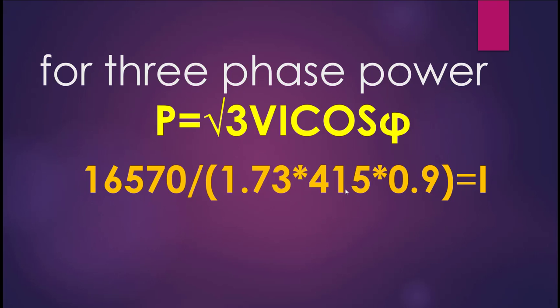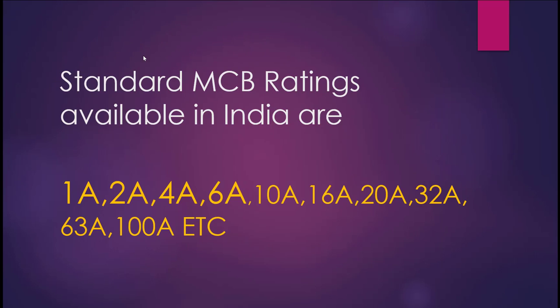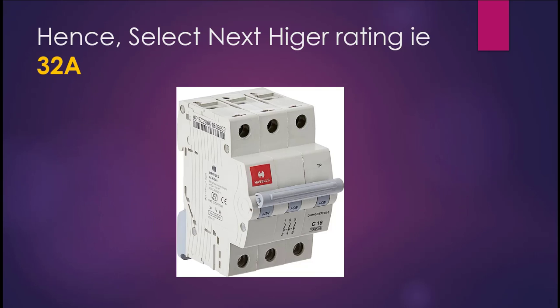For three-phase voltage we have phase-to-phase voltage of 415 volts. For the power factor, since we have some inductive load — we're using a motor and some heating equipment — we'll take cosφ as 0.9. So solving for I, we get approximately 25.64 amps. We need a three-phase MCB. Since 25.64 amps is not available as a standard rating in India, you have to go for the higher rating, which is 32 amps. So 32 amps will be the perfect MCB for your three-phase load.